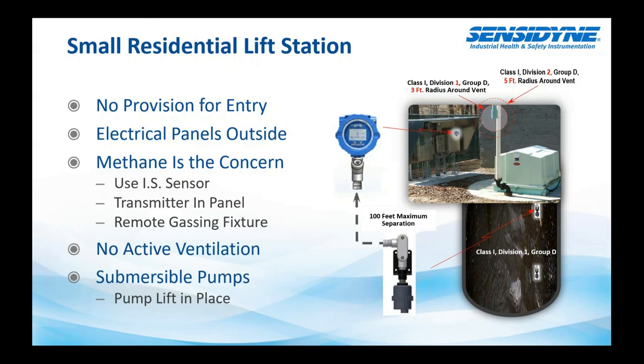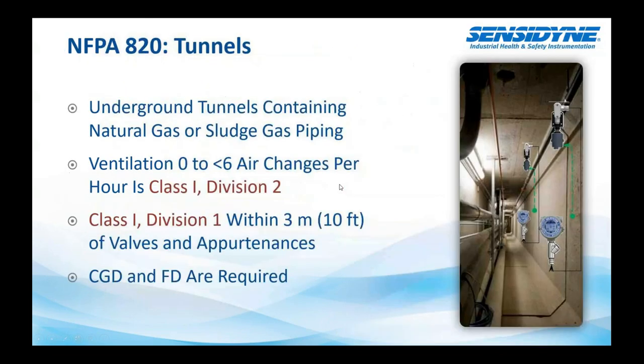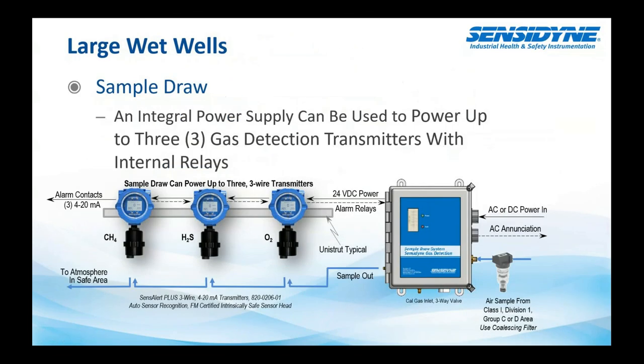And then another question as it relates to the wet wells with that sample draw system. You can use that sample draw system to pull out of a Div 1 or Div 2 environment, correct? Yeah, I'll cover that a little bit more, but you can draw from a Class 1 Div 1 area, and the sample draw itself is Class 1 Div 2 certified.